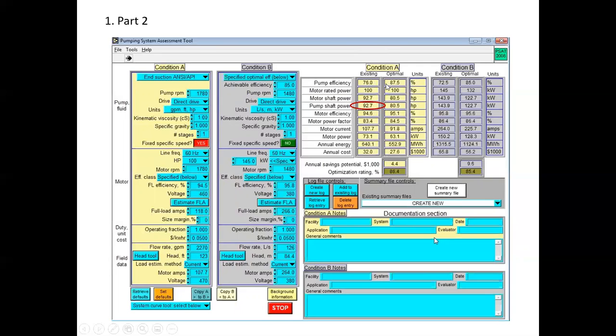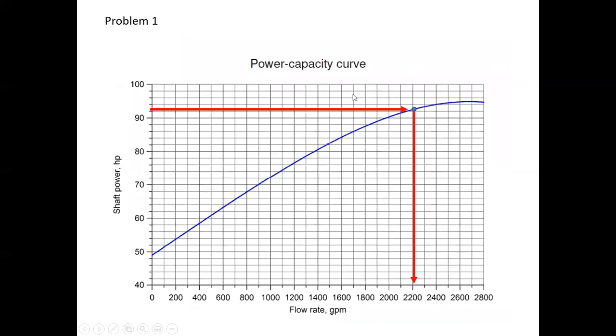The optimal, from the Hydraulic Institute algorithms, can see 87.5, but that's kind of neither here nor there, unless we decide to replace the pump, in which case we ought to be able to find something about this good. But at any rate, for this part, we're looking for the shaft power on the pump. So I've got 92.7 horsepower is what PSAT is estimating is coming out of the motor going into the pump.